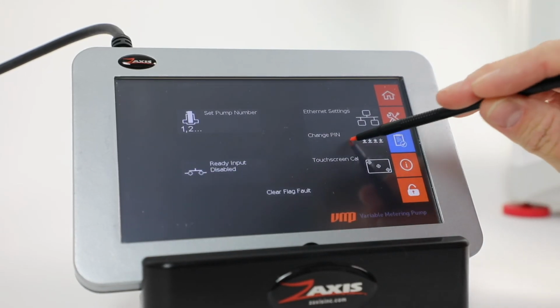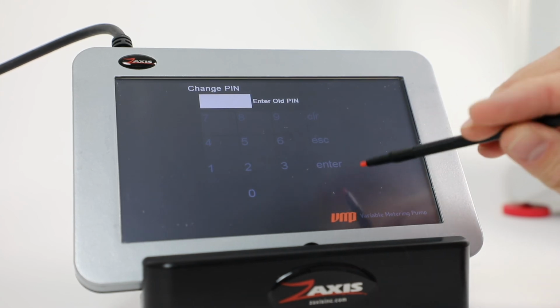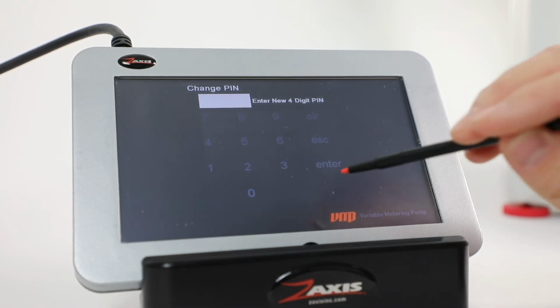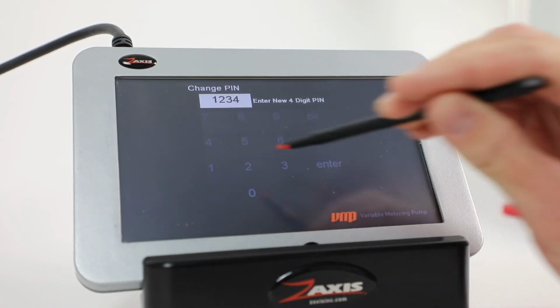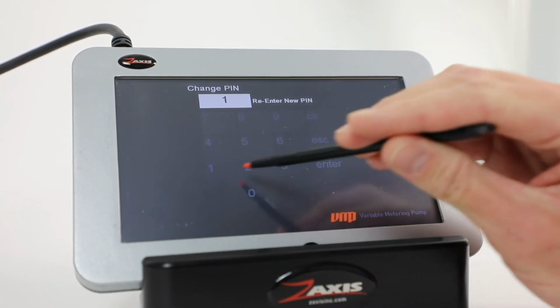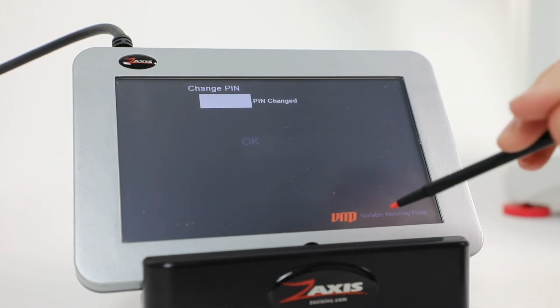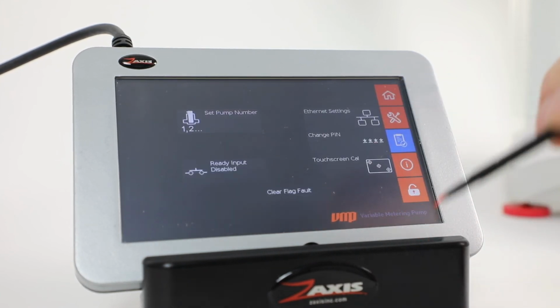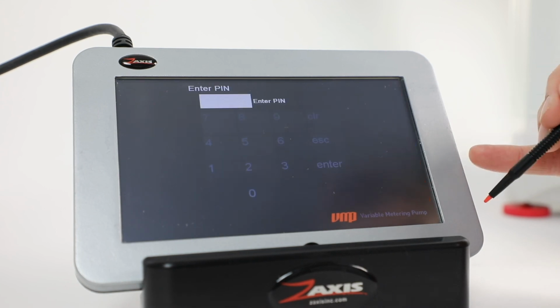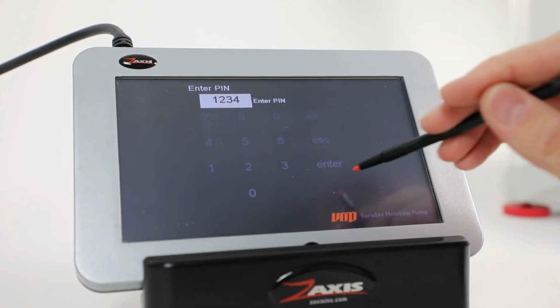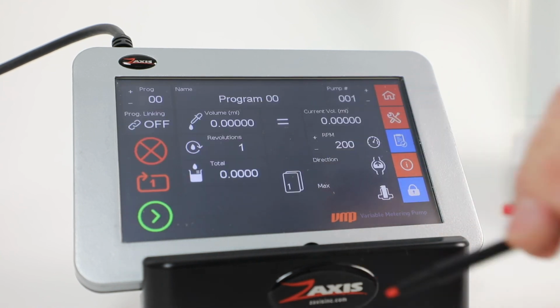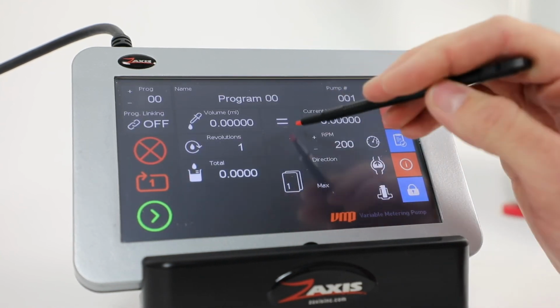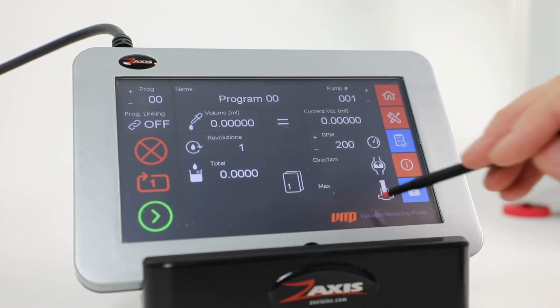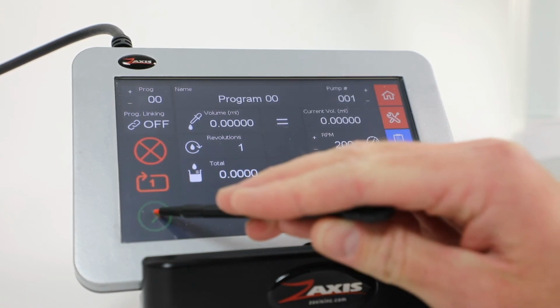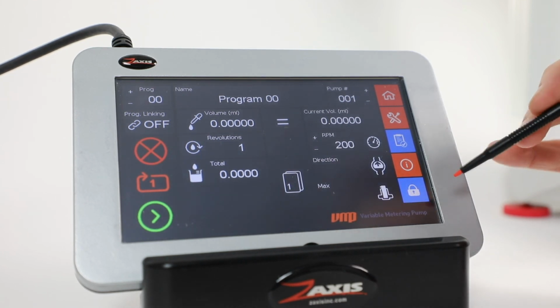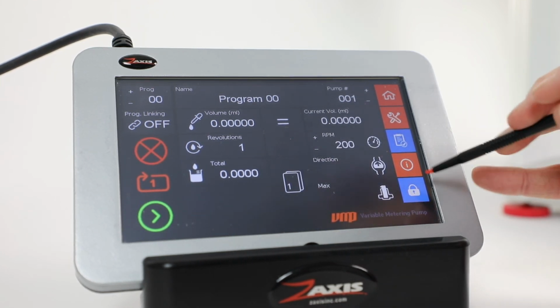Here you can change the pin. We'll change the pin. Since the old pin was blank, just enter. And the new pin will do 1, 2, 3, 4. And it'll make you re-enter it. And it'll say pin changed. And you should be able to lock the pump using that new pin that was just set. And this should stop anybody from changing programs or doing volume changes, but it will be able to run the pump. So if you want to set a recipe and make sure nobody changes it, that's the way to do it.